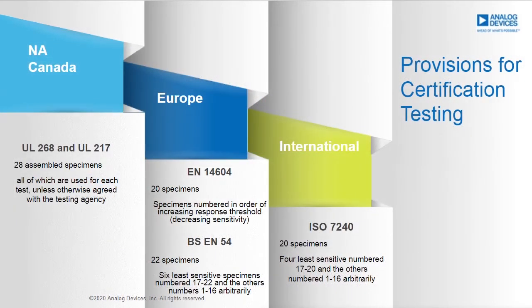And each regulation has a different set of rules for testing. For example, UL 268 and UL 217 require 28 test specimens, all of which are used for each test. For the other 3 standards, the specimens are numbered as detailed, and unique specimens are then required to pass specific tests. So as you can see, for global compliance, each test in each standard must be performed and standards cannot be overlapped. But it also extends to the conditions of test. However, EN 54, EN 14604, and ISO 7240 have identical requirements for the smoke tunnel and fire room, so the testing can at least be performed in the same location.